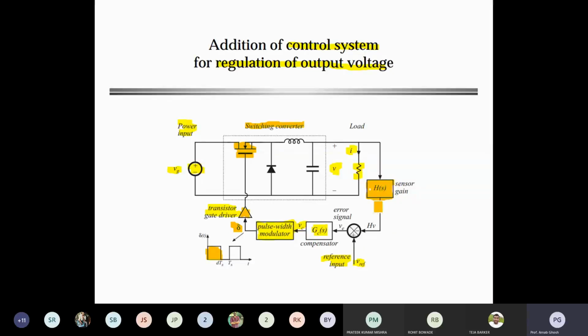Who is responsible for the scale down? Normally we use a transducer, a LEM transducer, LV25P maybe. For voltage there are voltage transducers; if you are sensing current, we use a current transducer, LA55-P I think. That is the LEM current transducer, a Hall effect sensor.